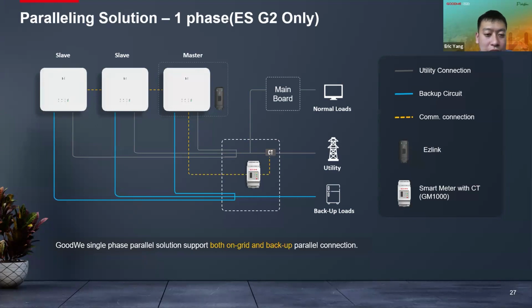And at the power cable connection, we can parallel the on-grid side output of the master and the slave inverters together to the utility and also connect to the on-grid load. And also the backup side of every inverter can be connected in parallel to the same backup load. And the maximum is 16 pieces in parallel: one master inverter and 15 slave inverters.